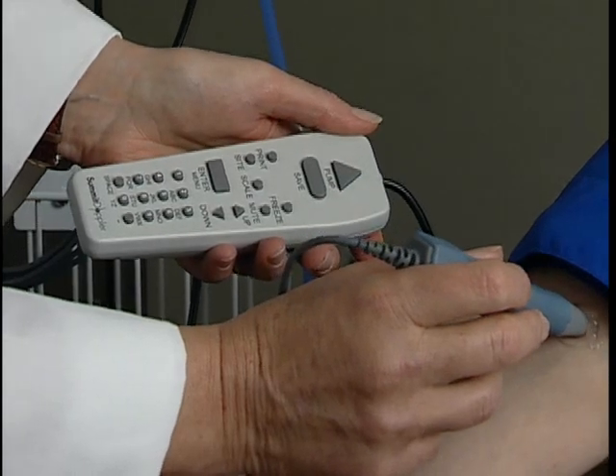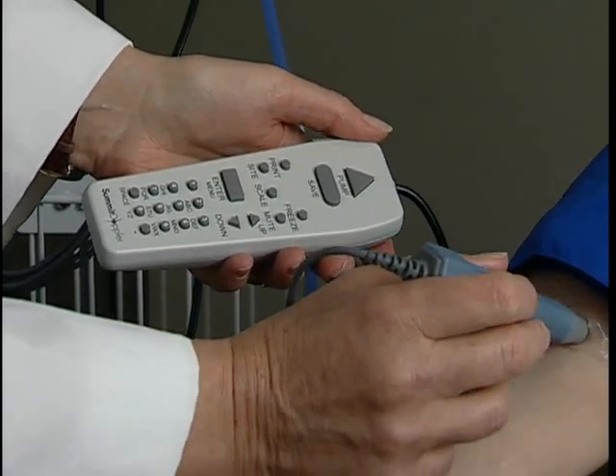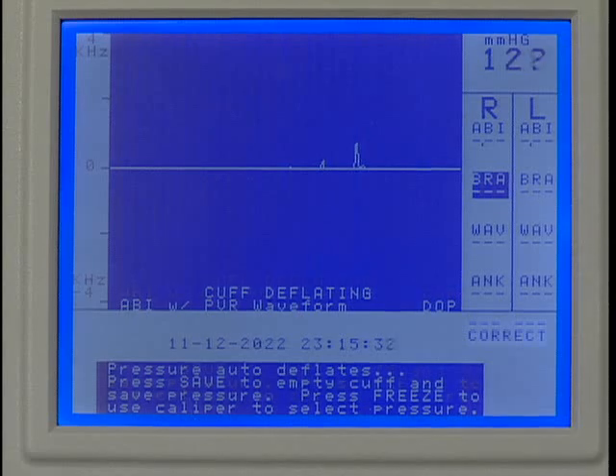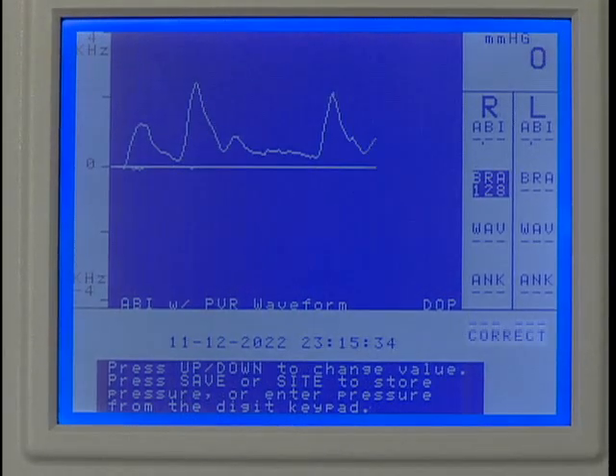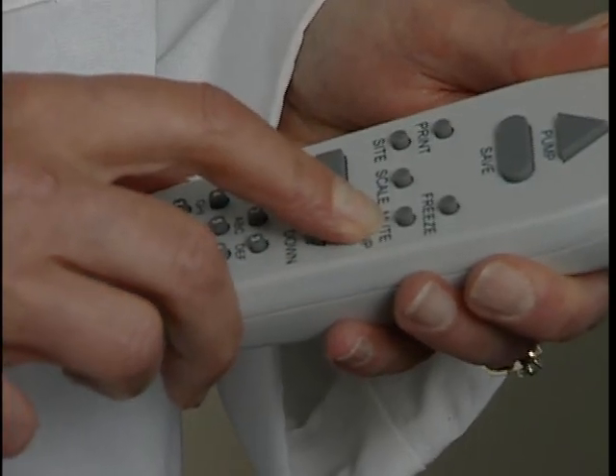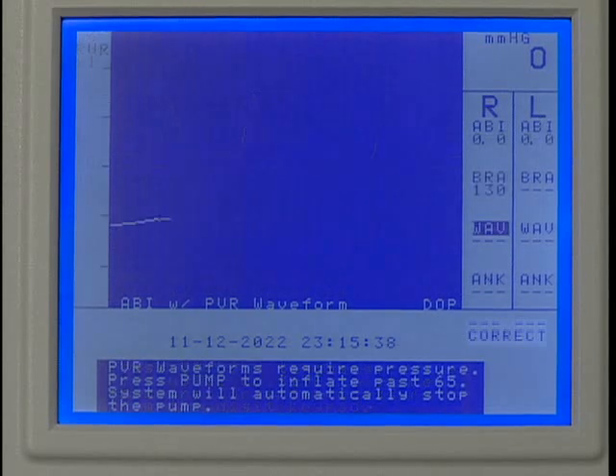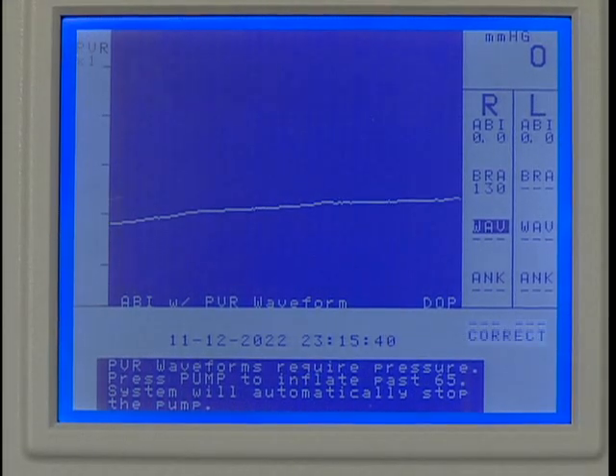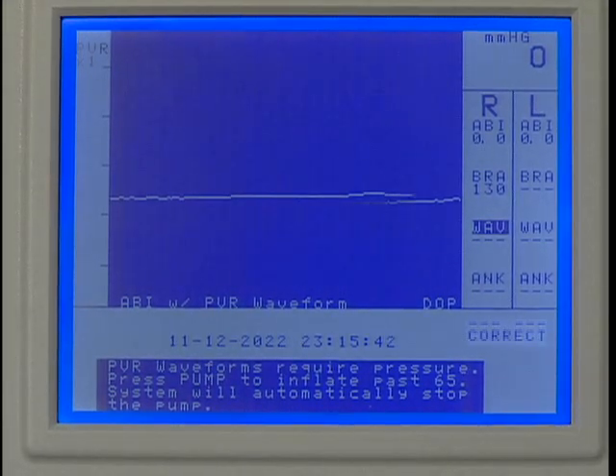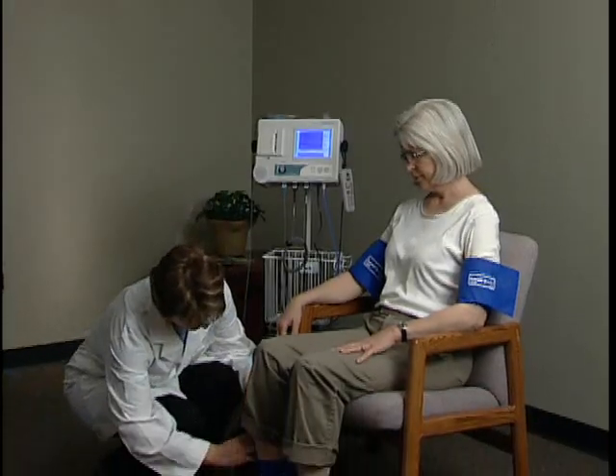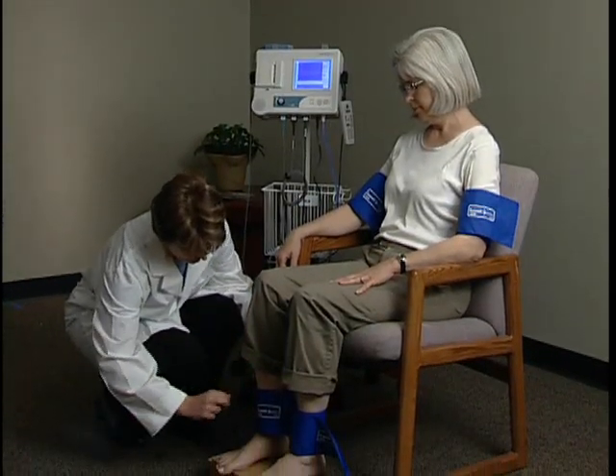Press Save when you hear the first pulsation return. If you are late pressing Save, adjust the pressure reading by using the up or down key as shown. Press Save to record the systolic pressure, and the marker will move to the next protocol location. Now we'll obtain the ankle waveform using PVR.